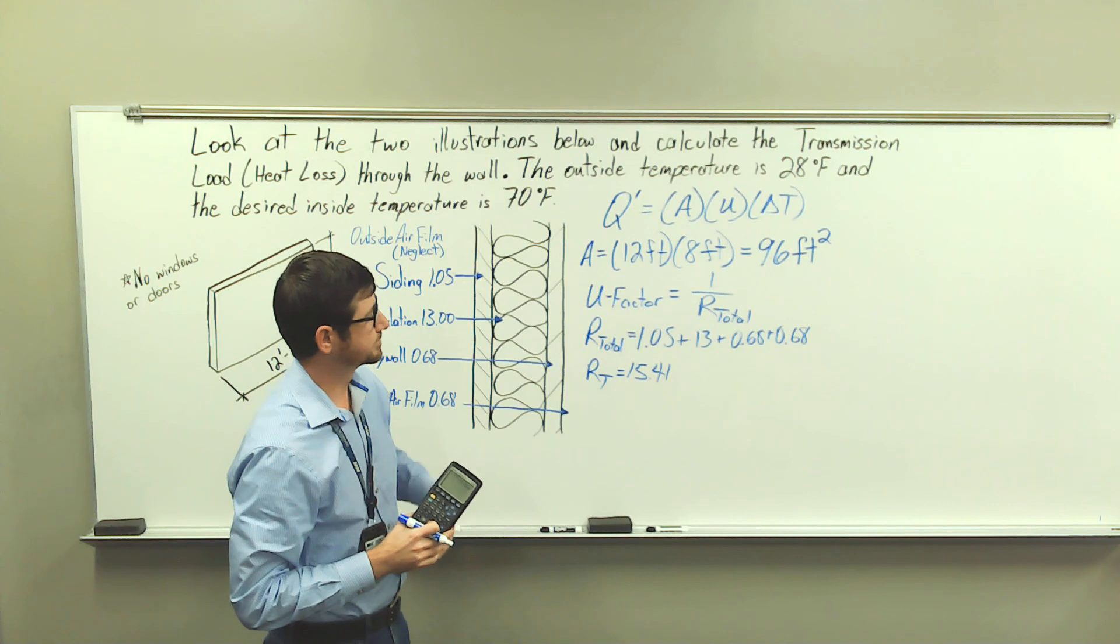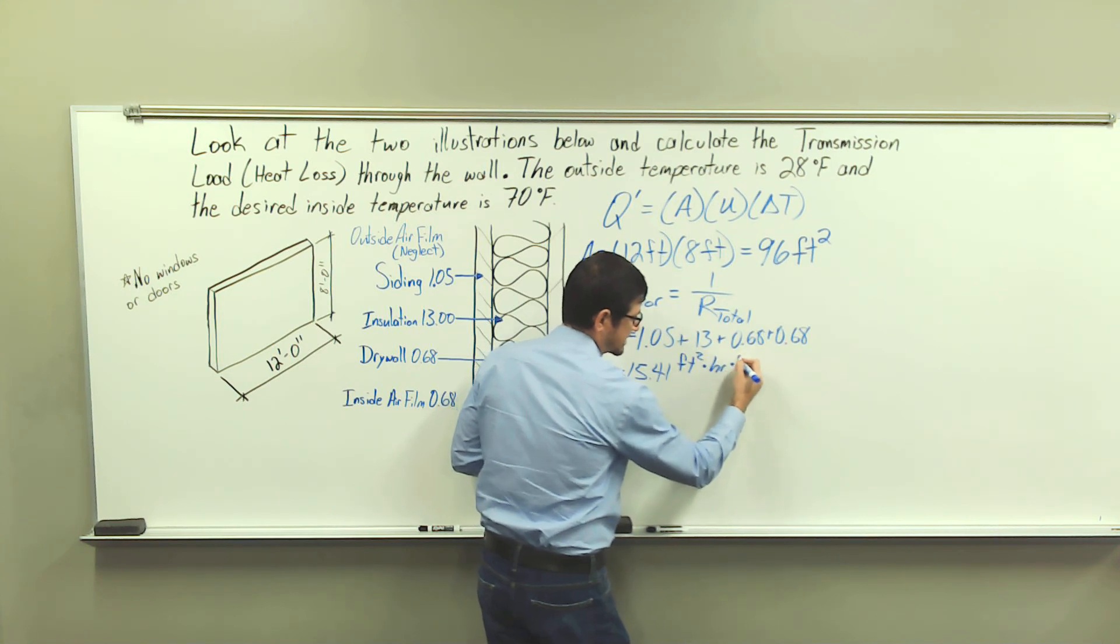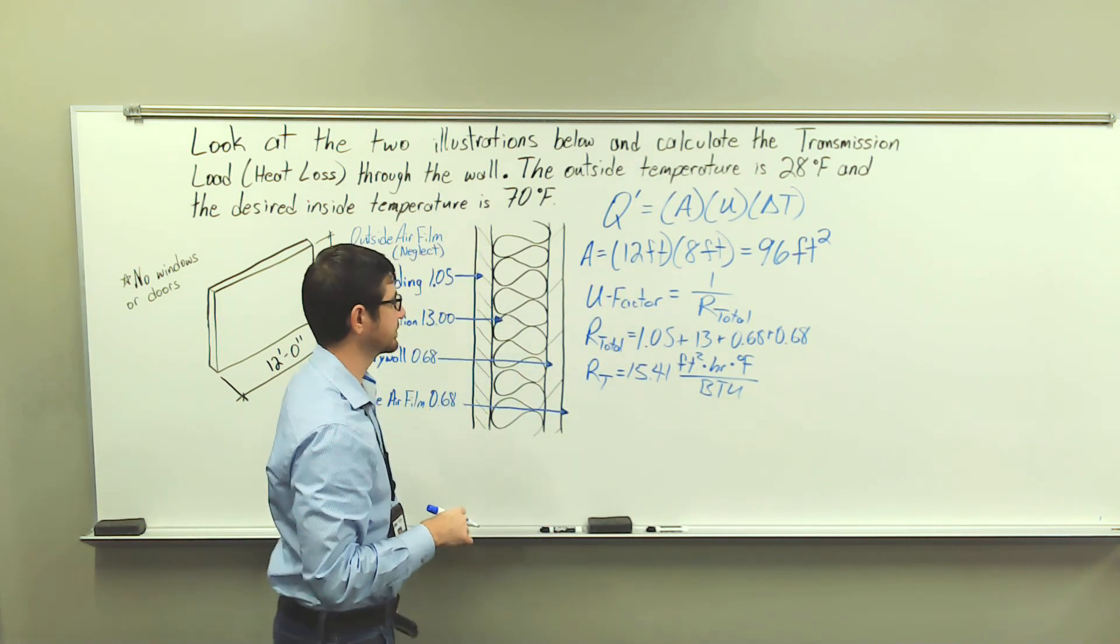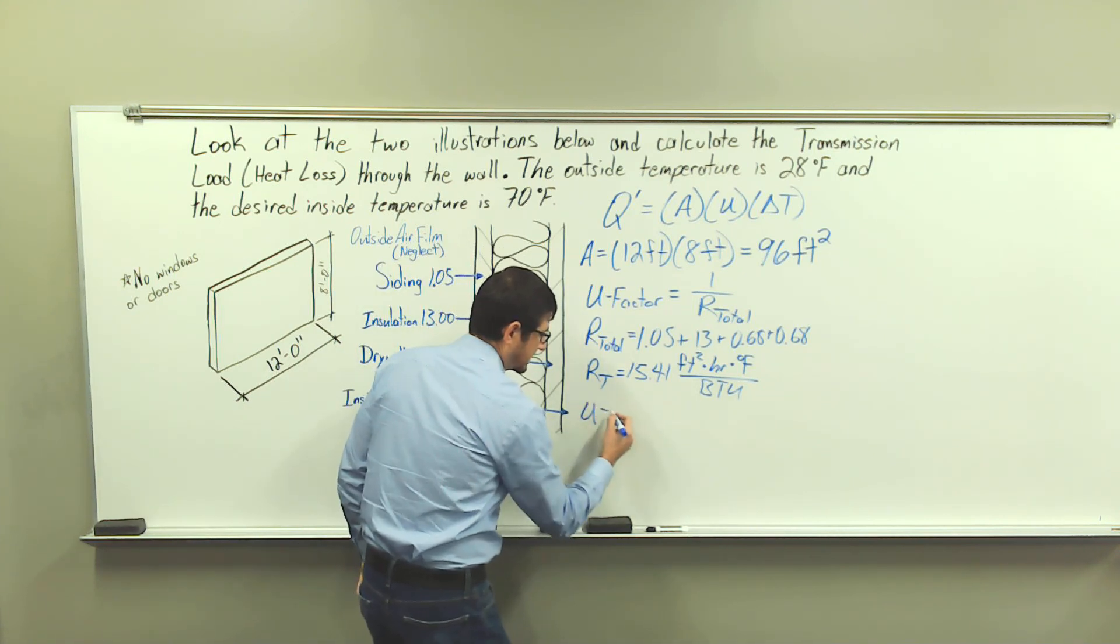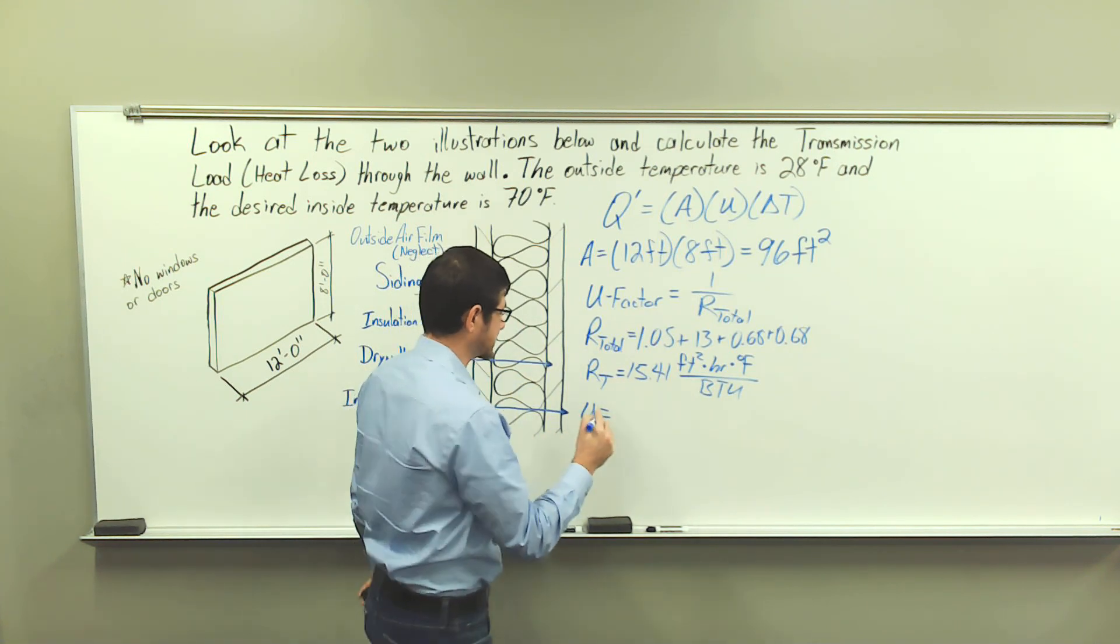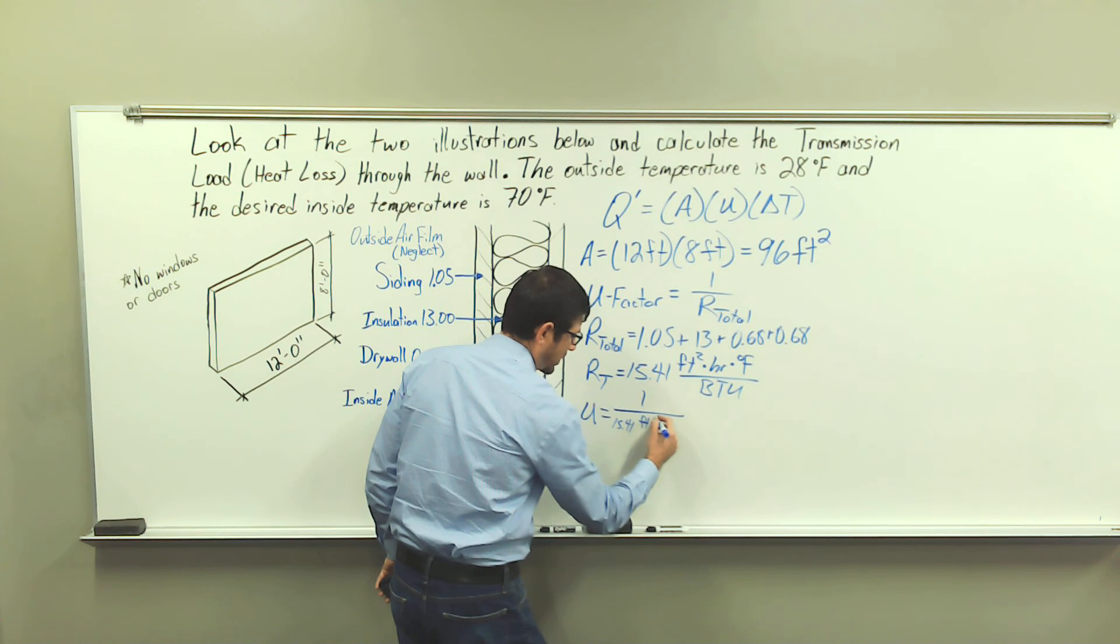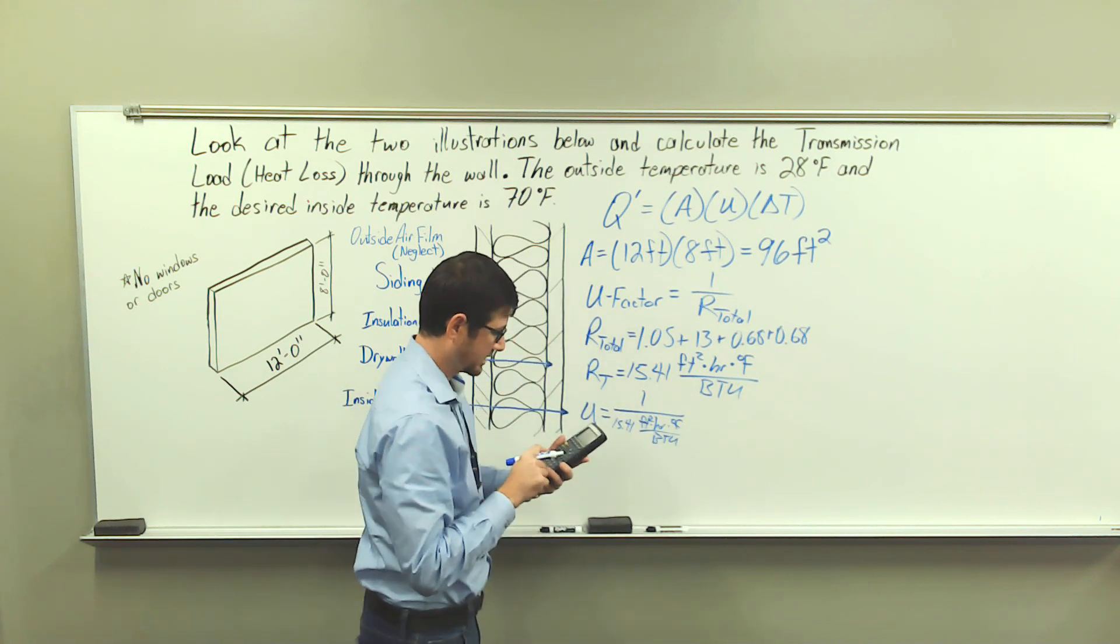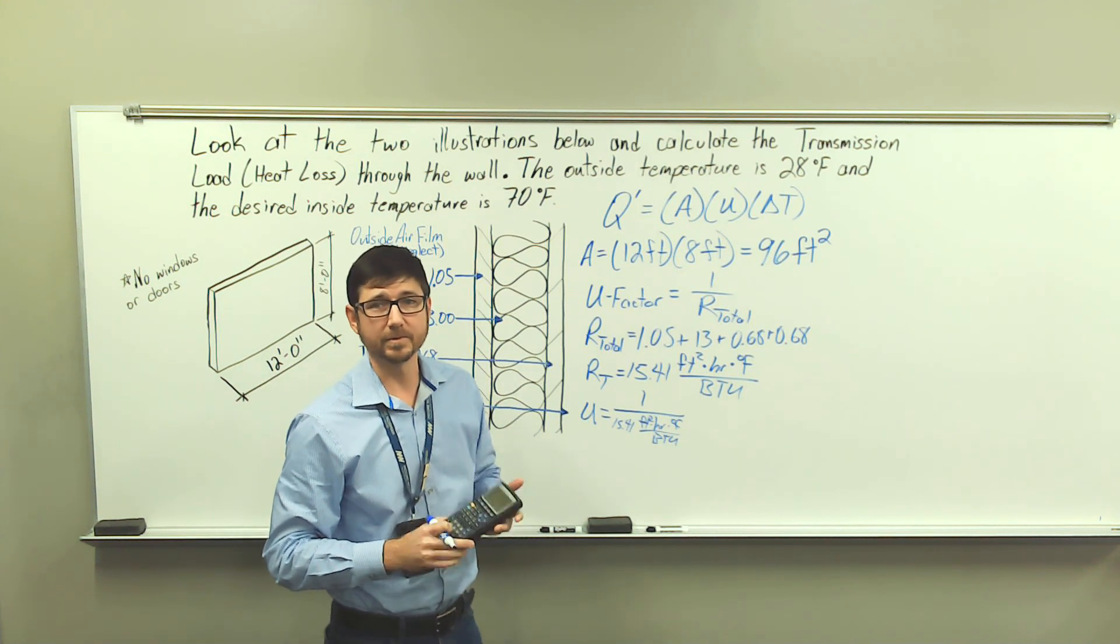Now the units on here, that's going to be foot squared times hour times degree Fahrenheit per BTU, or British thermal unit. So what we're going to do to calculate the U factor, this is going to be the inverse of our total R value. So 1 divided by 15.41. And what we're going to do, and I also listed in the notes, we are going to truncate at the thousandths place.